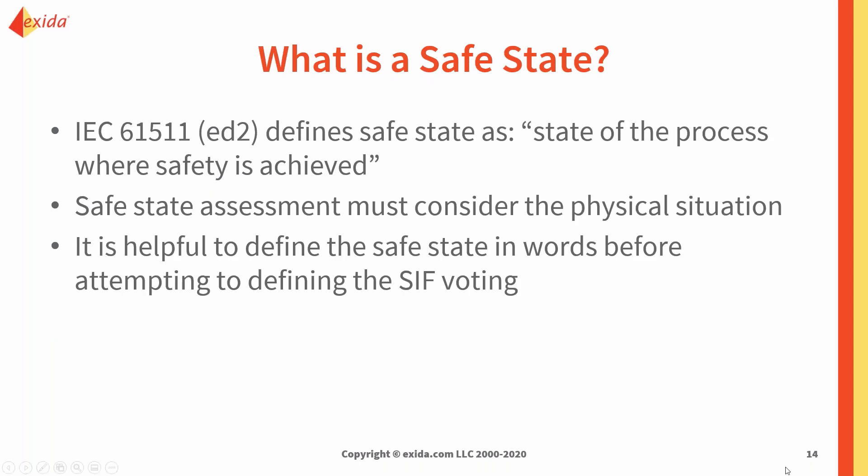Moving forward into the definition of a safe state: IEC 61511 defines it as the state of the process where safety is achieved. Whenever we have a safety instrumented function trip, certain activities need to occur to bring that into a safe condition. What we're looking for in the verification calculations is sufficient reliability to know that we're achieving that safe state within our SIL target. We need to consider the physical situation when looking at the safe state, as it does impact the voting.